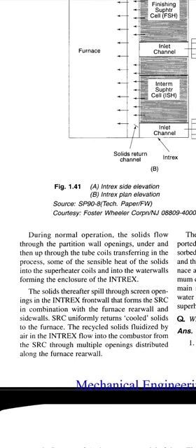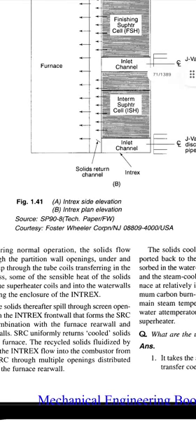The recycled solids, fluidized by air in the Intrex, flow into the combustor from the SRC through multiple openings distributed along the furnace rear wall.